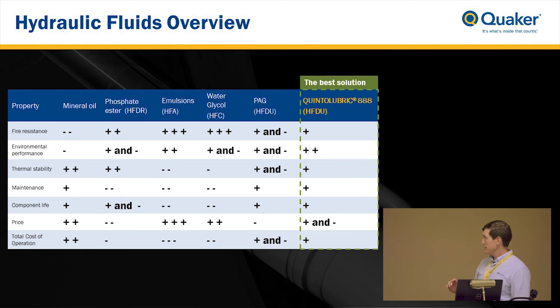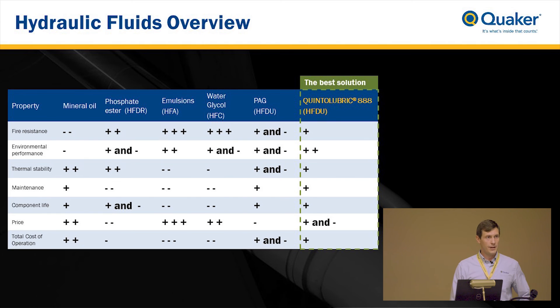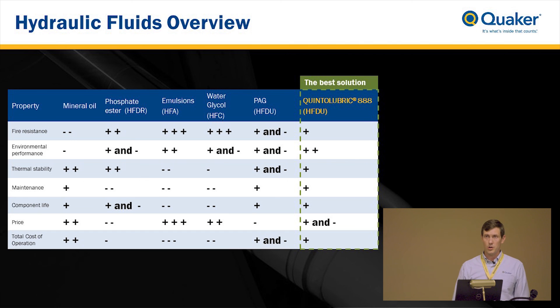The last chart is a snapshot of all the different characteristics showing pluses as pros and minuses as negatives for each product. Looking at the outer columns — mineral oil and the HFDU polyol ester — thermal stability, maintenance, component life, and everything really ticks the box with mineral oil, which is why it's the most used in the world. Its only negatives are that it is not fire resistant and not biodegradable. On the right side, HFDU ticks all the boxes — the only negative is it is more expensive than mineral oil, which is usually the only pushback seen with that product.